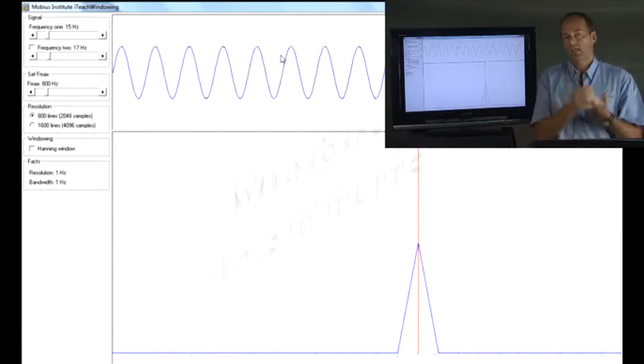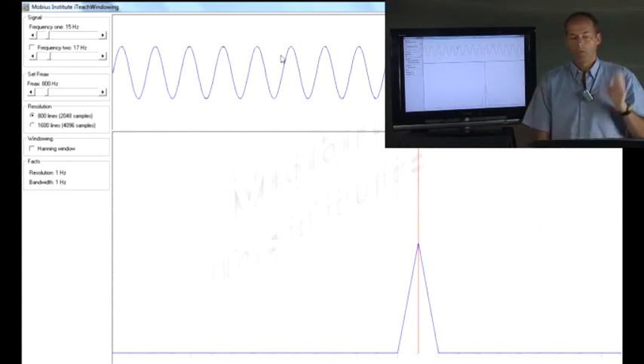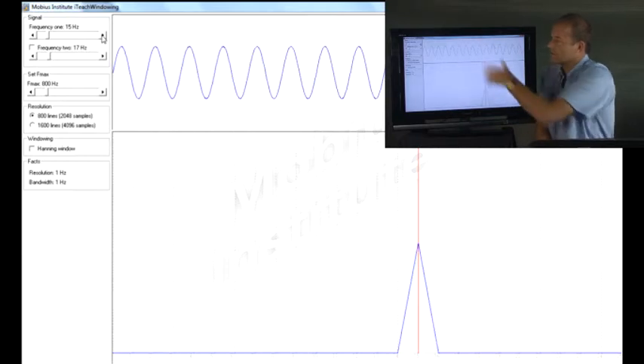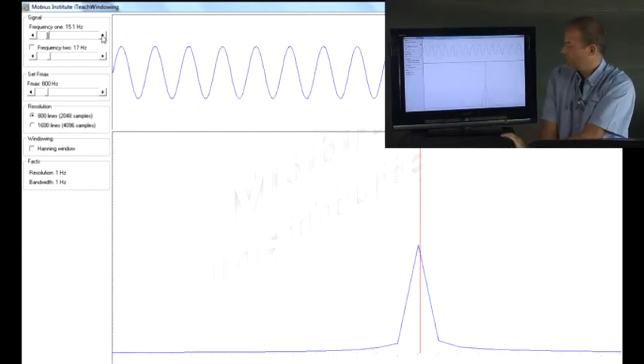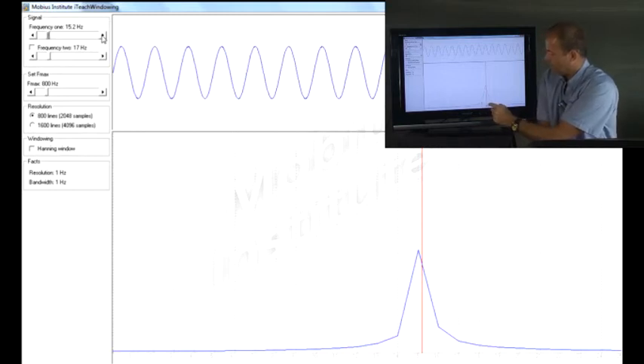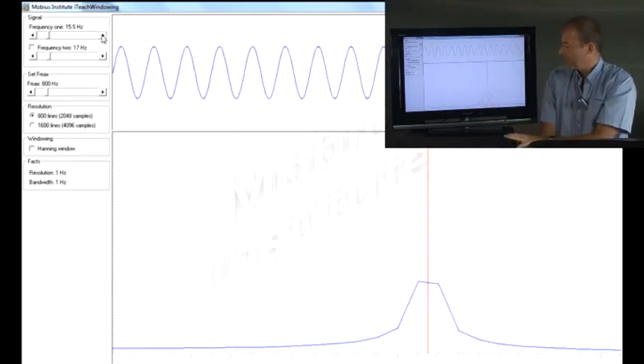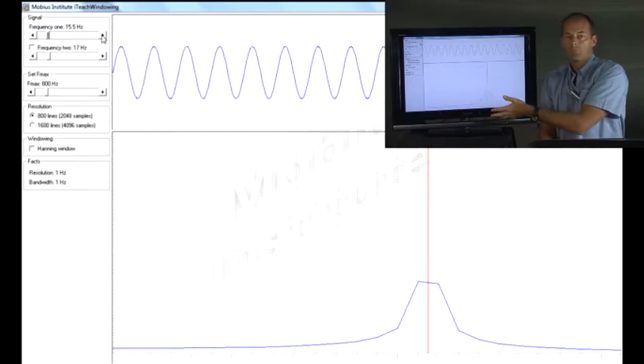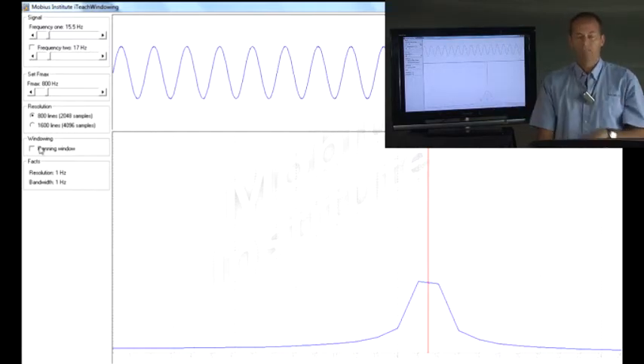800 lines, 800 hertz, that means there's one hertz between each bin. But what happens if the machine generates vibration that isn't exactly 15? What if it's 15.1 or 15.2? The red line is showing the exact frequency, but the spectrum can only give me a value at 14, at 15 and 16. And what we get is a real mess. Now, what I'm going to do, that's called leakage.